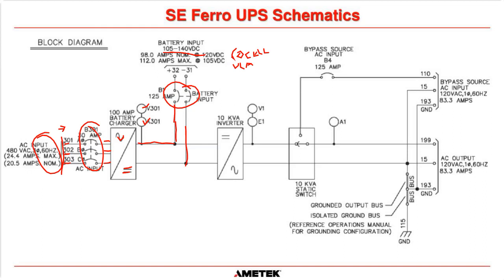And it's saying that nominally, if we had full load on this 10 kVA system, we would expect 98 amps. Okay. But we're saying that it can go up to 112 amps if we are discharging the battery and we go down to the final voltage level of 105 volts DC. So when you need to rate your cables, you have to keep that 112 in mind. So you have to size your cables outside this system to be able to carry 112 amps. Okay.